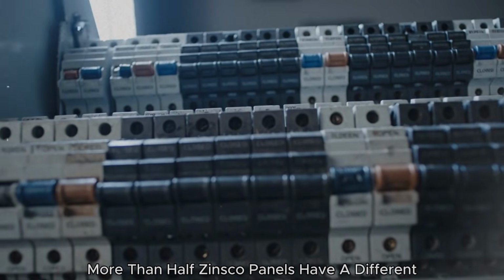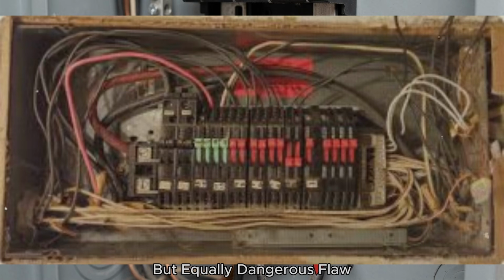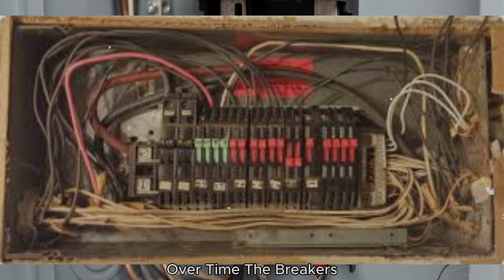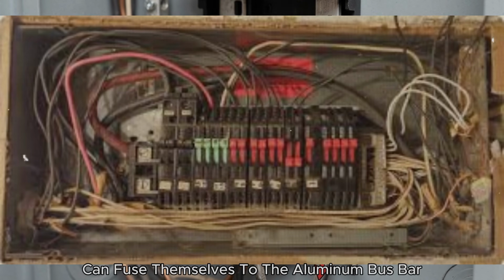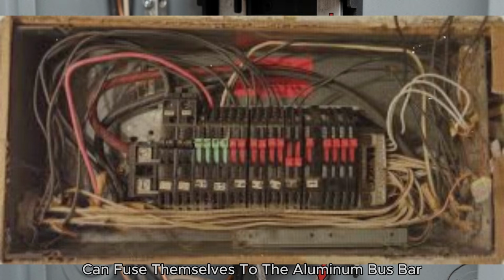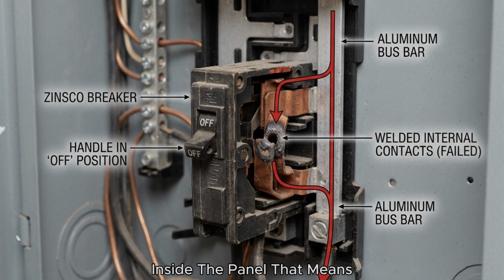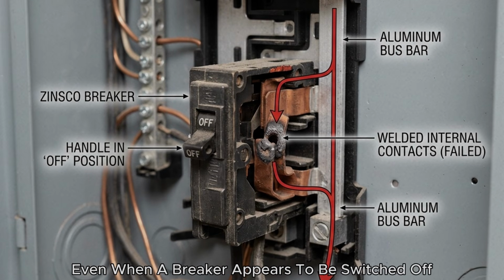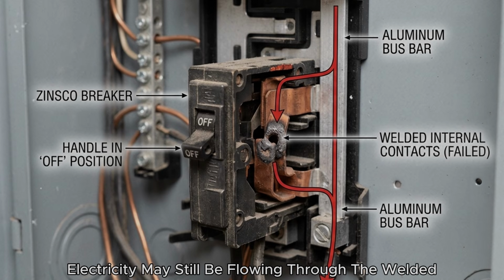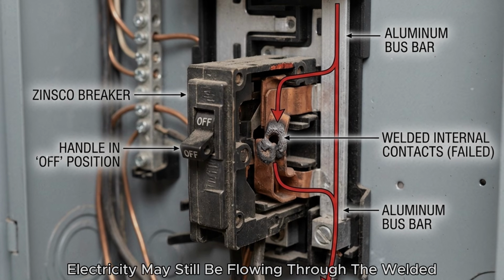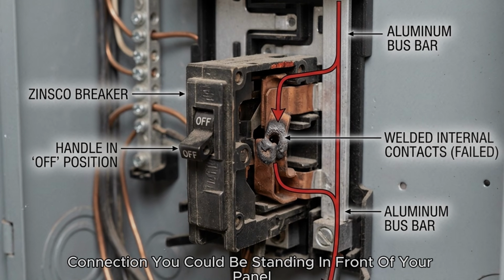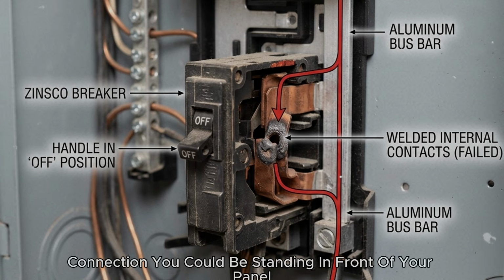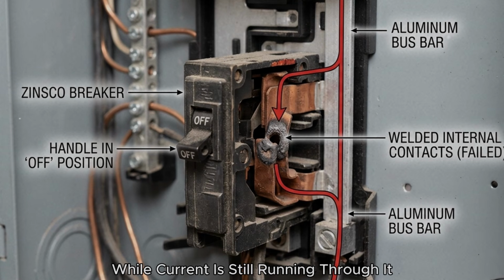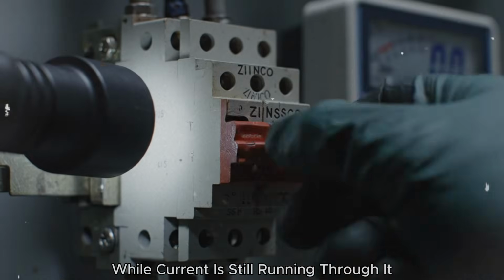Zinsco panels have a different but equally dangerous flaw. Over time, the breakers can fuse themselves to the aluminum bus bar inside the panel. That means even when a breaker appears to be switched off, electricity may still be flowing through the welded connection. You could be standing in front of your panel, thinking a circuit is dead, while current is still running through it. These are not theoretical risks.